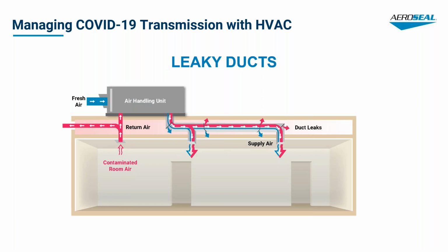So when you have leaky ductwork, all of that fresh air that you're trying to bring in to meet those ASHRAE standards, to meet all of these new CDC guidelines, is being leaked into the ceiling, basically, and it's not making it into the occupied space. And so all of that dilution that you're trying to have happen in that space is just not going to make it. So instead of having all of that fresh air make it in so that you increase the dilution, it's really just recirculating that same old air.